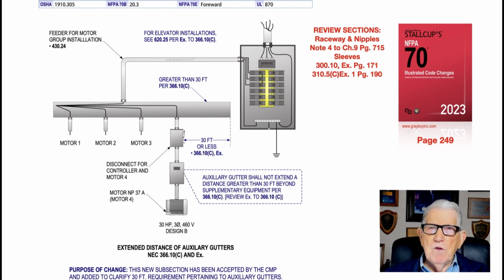Now, other review sections is a raceway and nipple. Now, you see the disconnect below the auxiliary gutter. If that's 2 foot or less in length, it's a nipple. You get a 60% fill, and you do not have to derate for current carrying conductors. But the raceway above there, extending from the panel board to the auxiliary gutter, is over 2 foot. So it's a raceway, as explained in Note 4 to Chapter 9 on page 715 of the NEC.